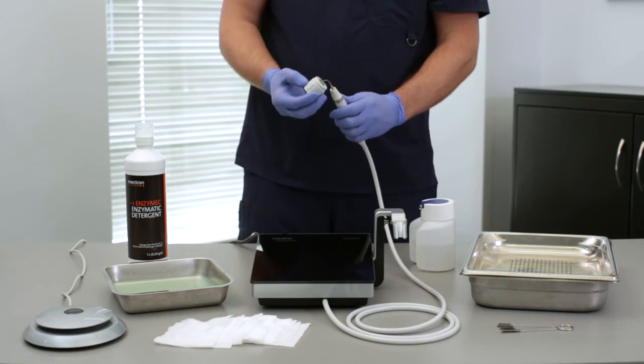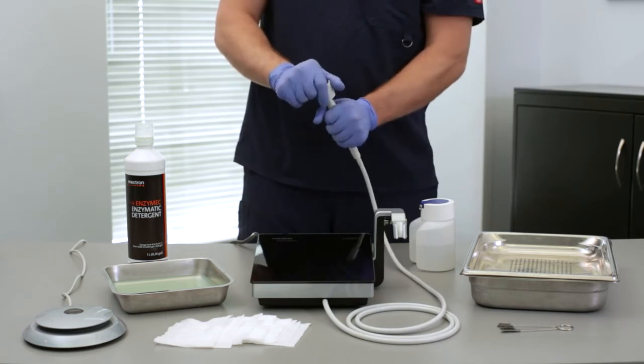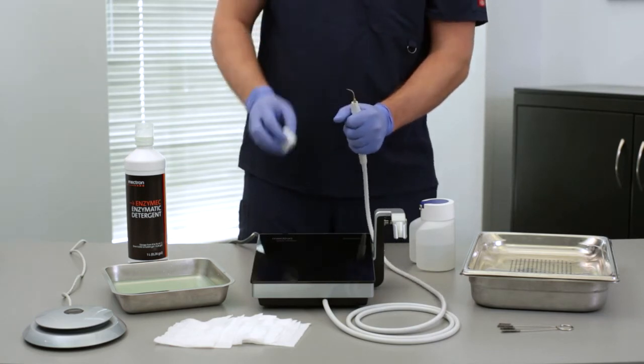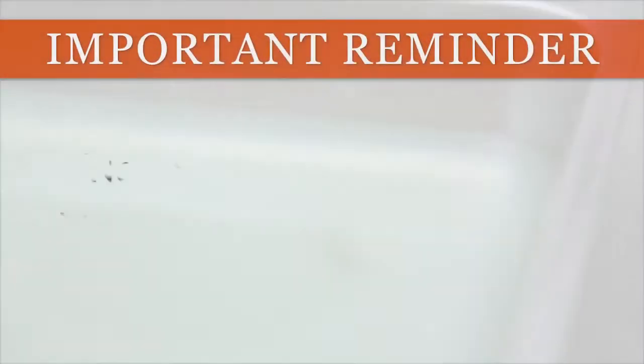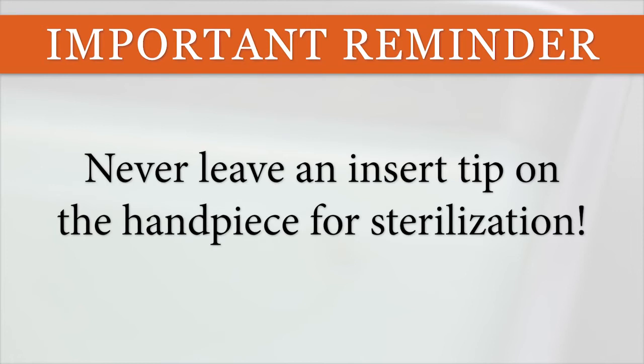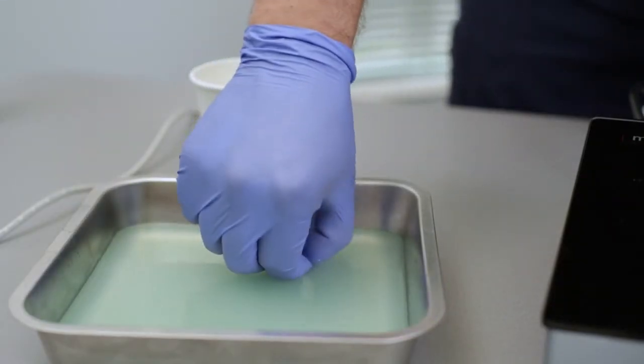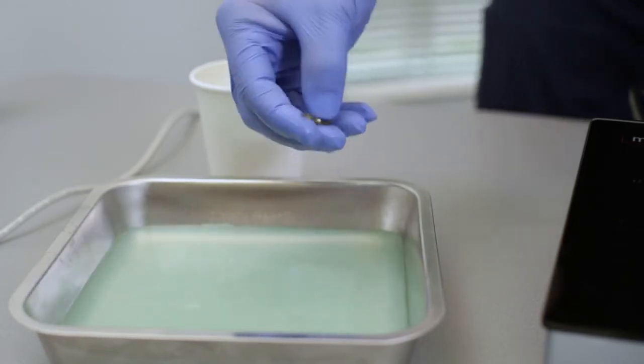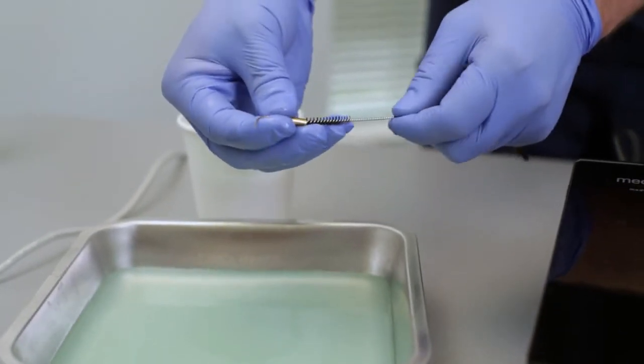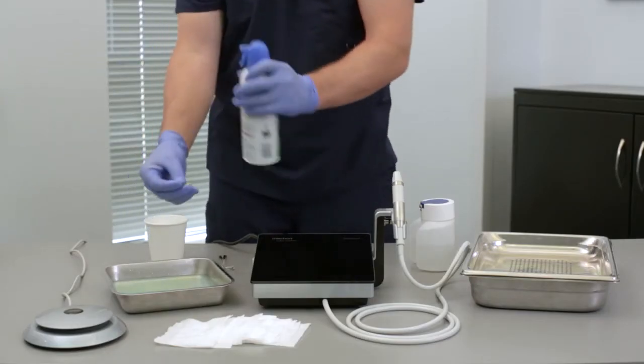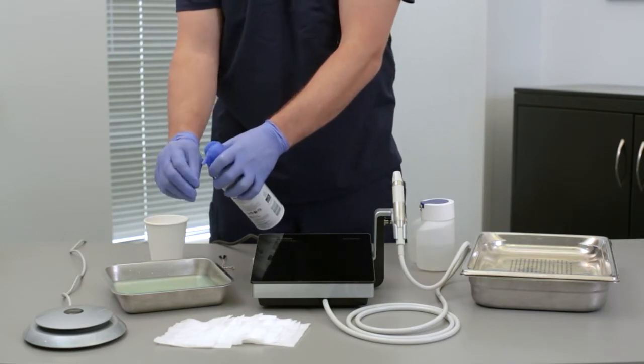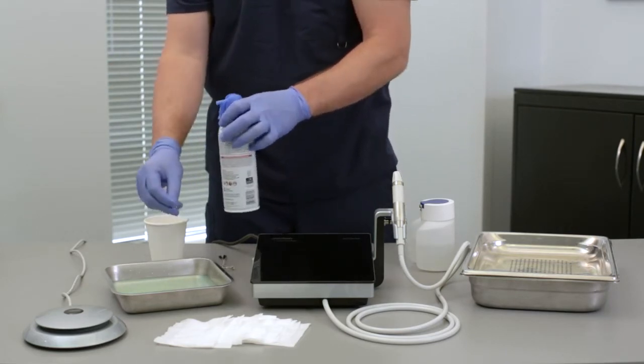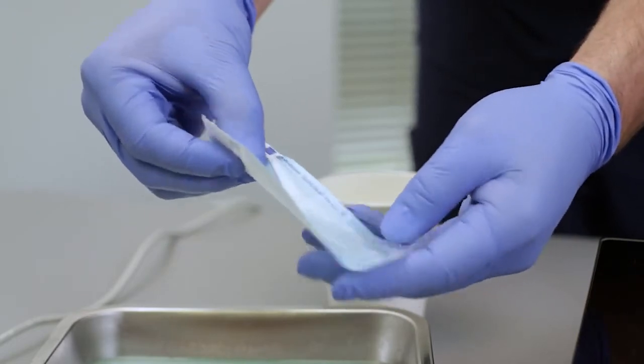Unscrew the insert tip from the handpiece with the torque wrench by turning it counterclockwise, and then place the insert tip into the enzymatic detergent to soak. Never leave an insert tip on the handpiece for sterilization. After soaking is complete, remove any debris using a soft bristled brush and rinse with water. Ensure that the insert tip is dry by blowing compressed air into the base of the tip, then place the tip into its own sterilization pouch.